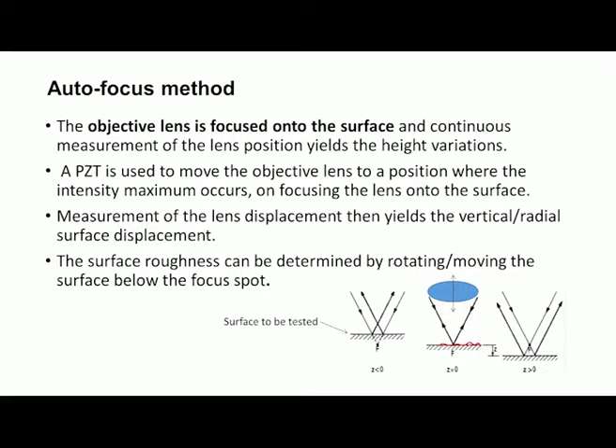Now, in the intensity method, the objective lens is fixed, it is not moved, even with the variations of the asperities on the workpiece surface. If a particular point is exactly at the focal point, the reflected light intensity will be maximum. If a particular point is not at the focal point, you can see the focal point is somewhere here, whereas the point on the surface is somewhere here, so the reflected light intensity will not be maximum.